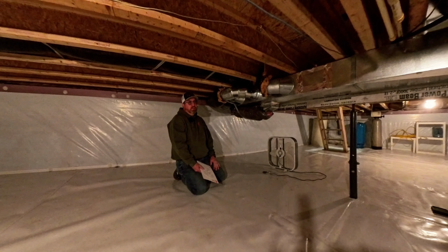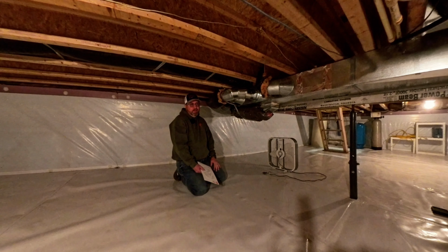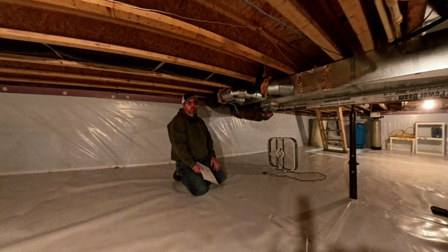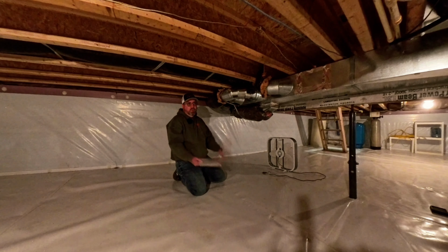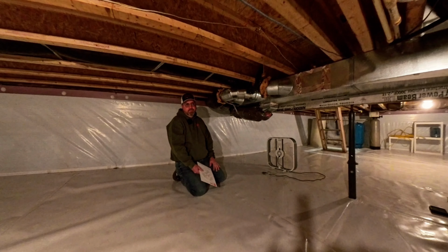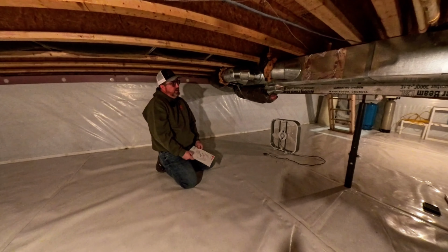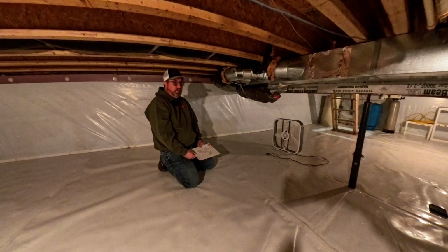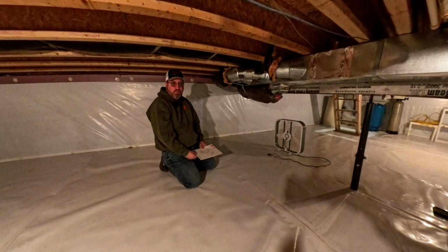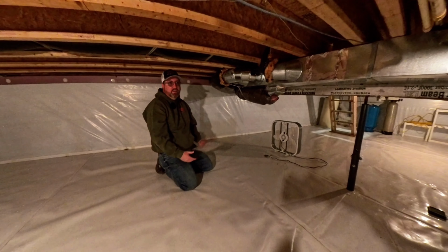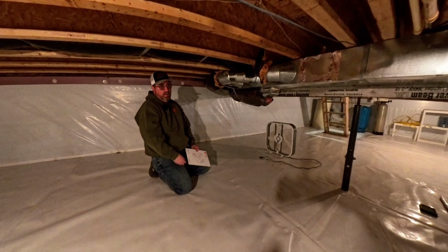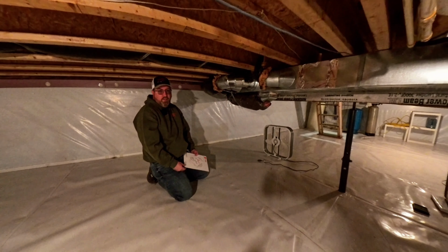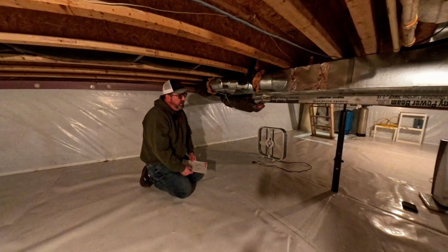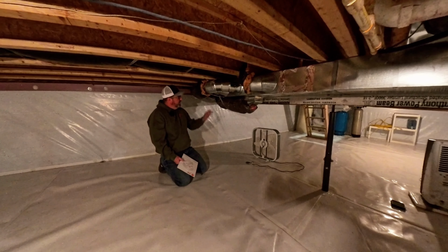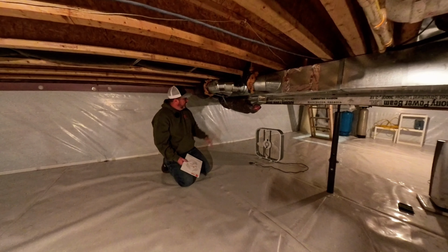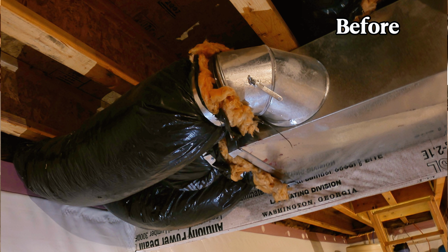If the supply duct system is poorly designed and runs out of the end cap, we're going to have uneven airflow throughout the entire supply system. We are obviously dealing with existing ductwork and duct runs, and without completely going through the whole house and tearing it all out and starting from scratch, we're working with what was here but trying to make improvements on what was here. So previously, 3 of these duct runs that you see on the side of the ductwork and the bottom of the ductwork were straight out of the end cap.